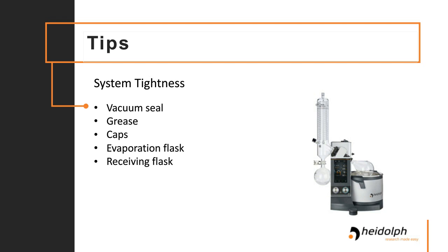And if you do not find the reason for the leakage directly on the rotary evaporator, it sometimes makes sense to also have a closer look at the peripheral devices and materials, especially the tubing. If you use rubber tubing, sometimes the UV radiation over time leads to cracks inside and can also lead to a leakage inside of the system.